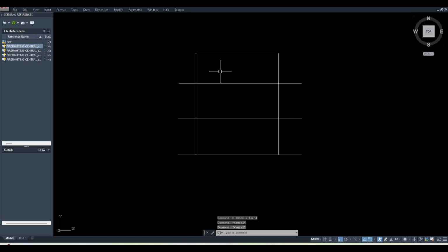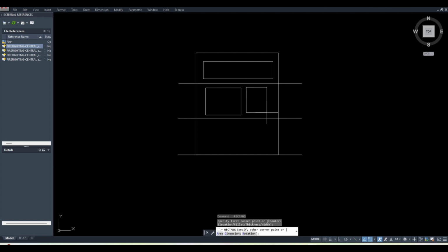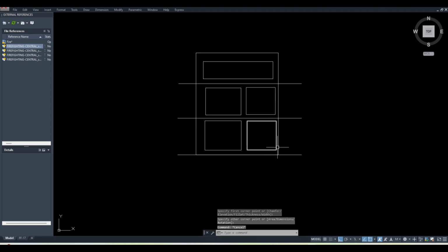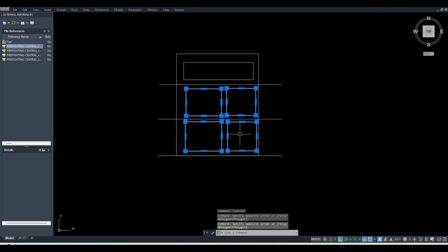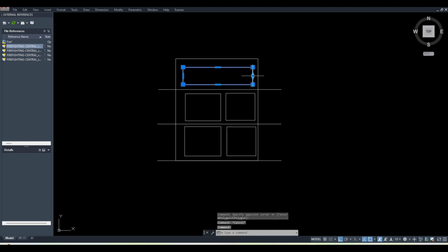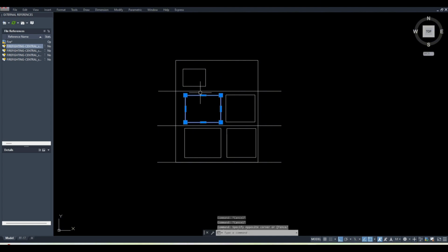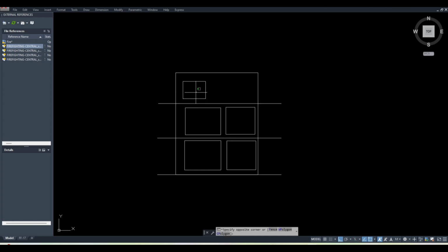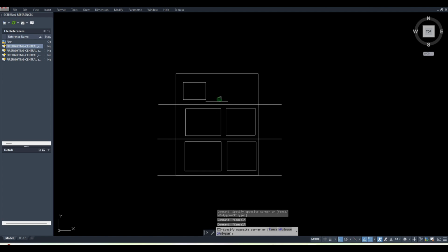It means suppose the area of this floor is not more than 4,831 meter square, we can convert this as one zone. And then here we can convert this into two zones. So total five zones, right? Now even if the top floor area is 100 meter square, you cannot combine it with this one. Suppose this is 4,500 square meter, so still we have 300 or so left out. We will think logically that we can combine this zone with this, but no, each floor has to be on a separate zone.